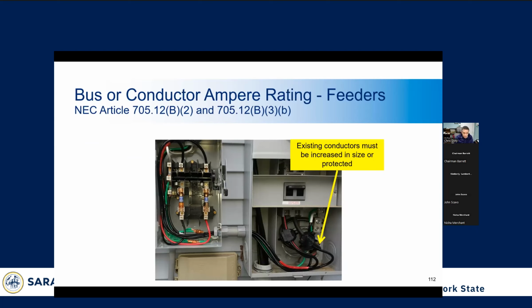Here's a real life example of the previous slide. We see the interconnection on the load side of the 200 amp breaker. So this is where the load is coming in. And this is at an apartment building where the apartment panel didn't have a main breaker. This is in the meter pan, and it has the integral disconnect. So the existing conductors can be strained by this additional current. Possible solutions include increasing the size of the conductors and the bus bar for the new additional current, or having additional protection by adding an overcurrent protection device before the load, such as a main breaker in the panel this feeds. That's pretty expensive, but it's a potential solution.